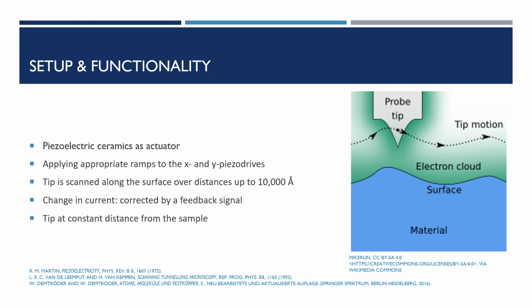And the piezoelectric ceramics are used as the actuator. They combine a large scanning range with a minimum deflection in the sub-angstrom range. The underlying piezoelectric effect is a generation of electrical polarization by applying stress to a crystal. It also works the other way around. These ceramic cylinders change their length. They are enlarged or reduced when an electrical voltage is applied, so when current flows. And this property is used to adjust the position of the metal tip very precisely on the one hand, and on the other hand, to keep the metal tip at a constant distance from the sample.